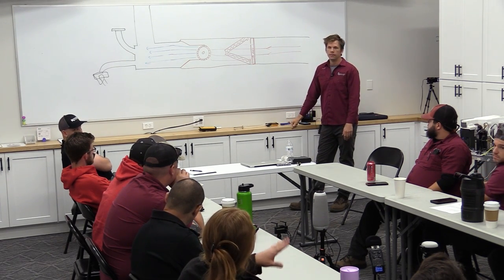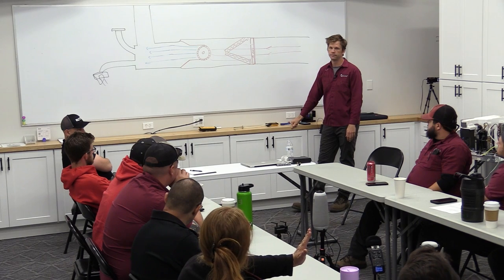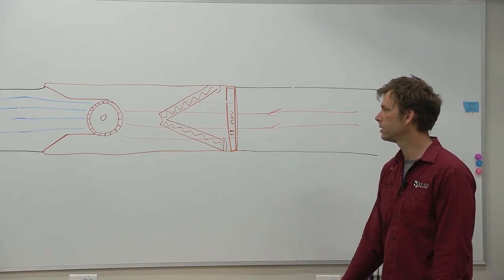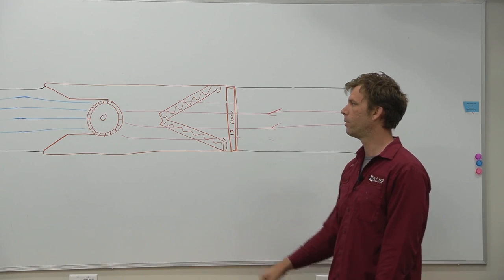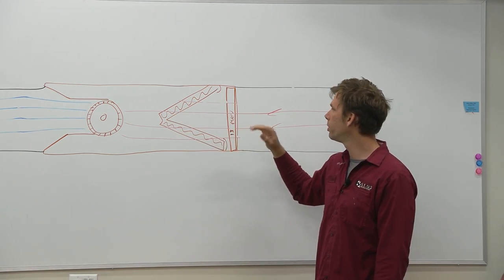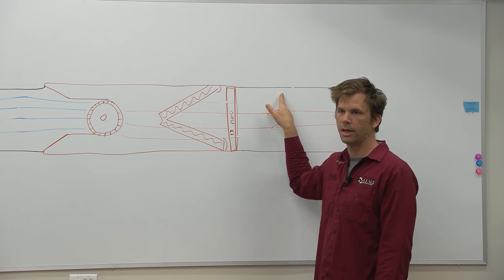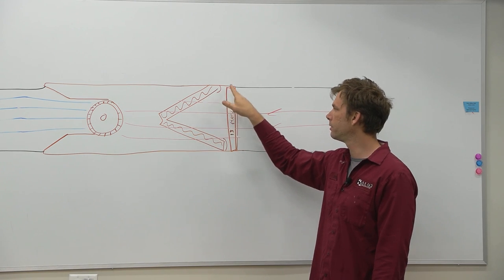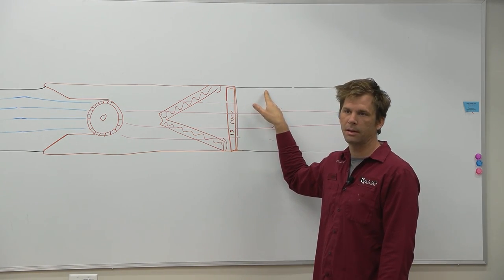Could you just pull out the filter and still measure further away? Will that affect the measurement? Yes, you can. If you're looking for how is my system actually operating without the filter, you can pull it out and measure here. You're not going to be able to measure how much your coil is affecting it, but your filter, you can pull it out and compare.